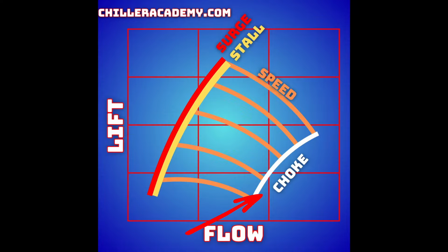Now a choke is when we have really high flow but too little lift. This is a situation where the refrigerant flow becomes unstable as well, because we do need to maintain some lift in order to get the impeller to work properly. And I'll admit, I struggle. I'm still trying to find a clear way to communicate what choke is and how it's different, because these symptoms are similar in many ways, while it's technically not the same thing. We are choking the impeller versus having a surge reversal of flow. I'm still trying to figure out how to explain this in a way that makes sense. Anyway, a choke is on the other side of that.